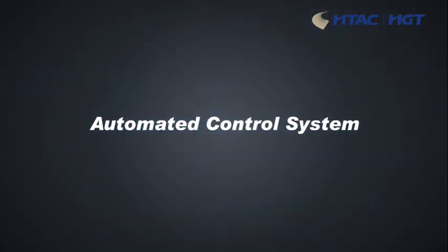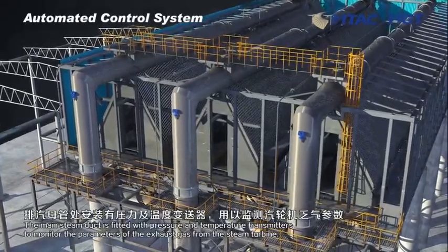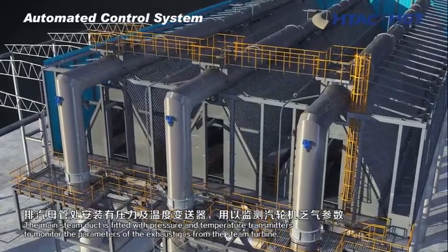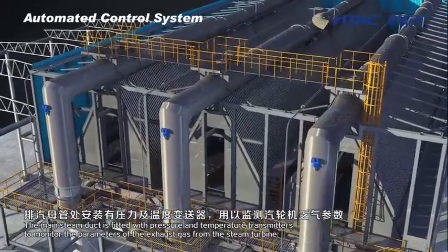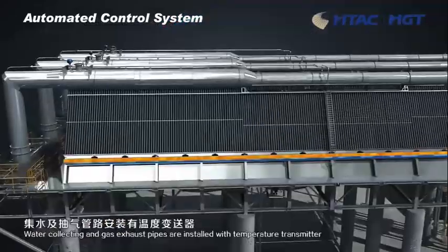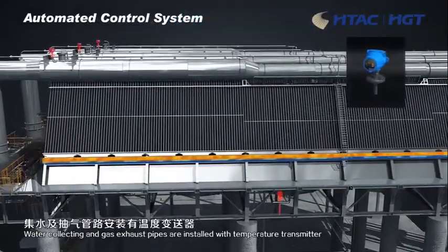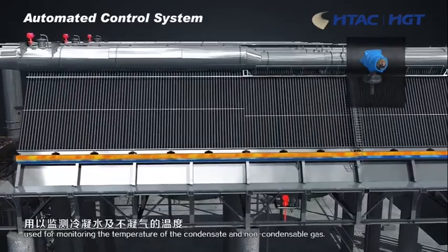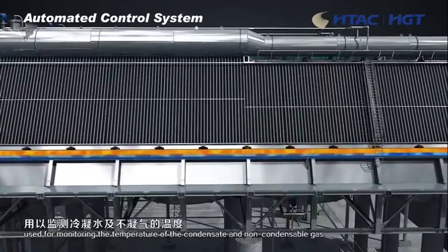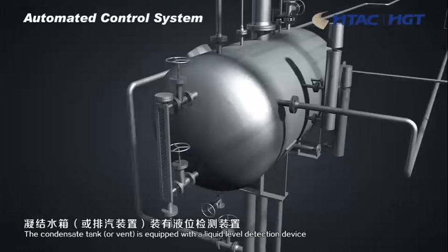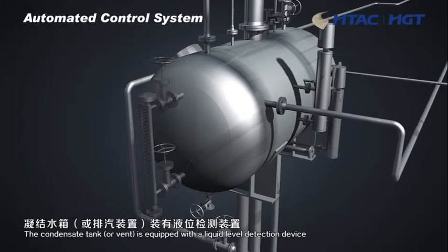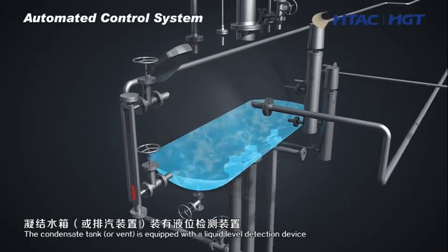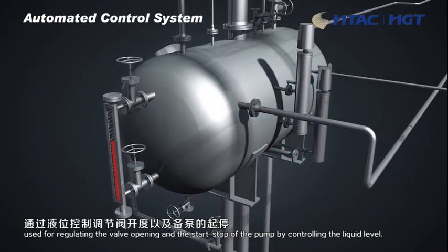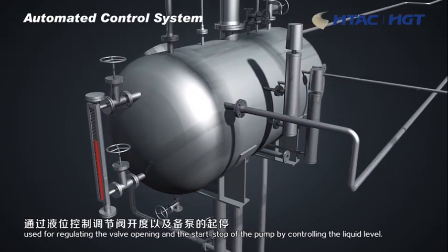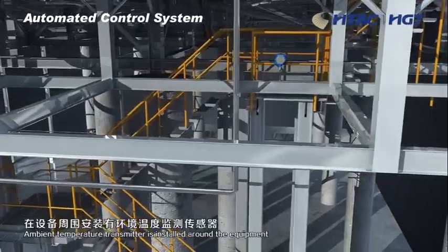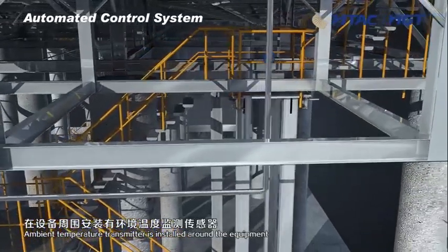Automated control system. The main steam duct is fitted with pressure and temperature transmitters to monitor the parameters of the exhaust gas from the steam turbine. Water collecting and gas exhaust pipes are installed with a temperature transmitter, used for monitoring the temperature of the condensate and non-condensable gas. The condensate tank or vent is equipped with a liquid level detection device, used for regulating the valve opening and the start-stop of the pump by controlling the liquid level. Ambient temperature transmitter is installed around the equipment.